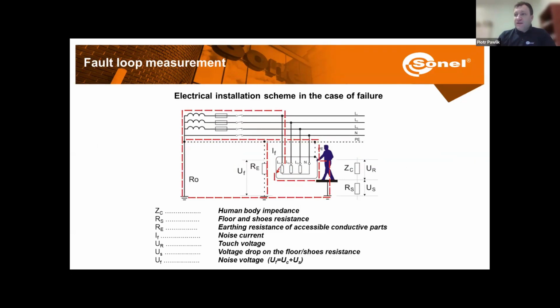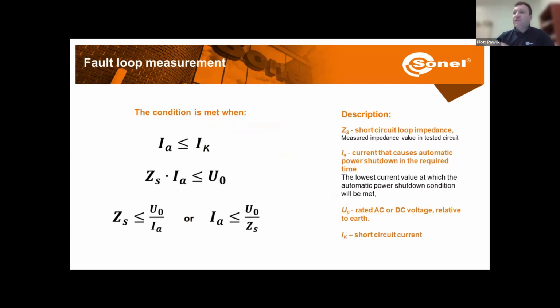And all of these currents together create a fault current. So this is a current flowing through the ground in case of a fault situation. And the whole idea is that fault current should be higher than the current triggering the breaker. So this is pretty obvious. We have overcurrent protection, so in case the current flowing in case of a fault is higher than the limit, the breaker will work. And this way the people are safe, and it will also prevent any overheating or fires.